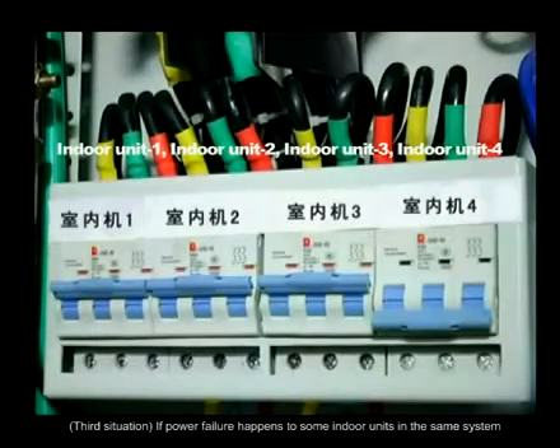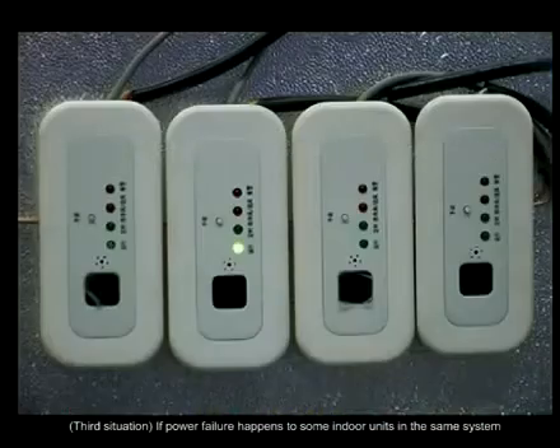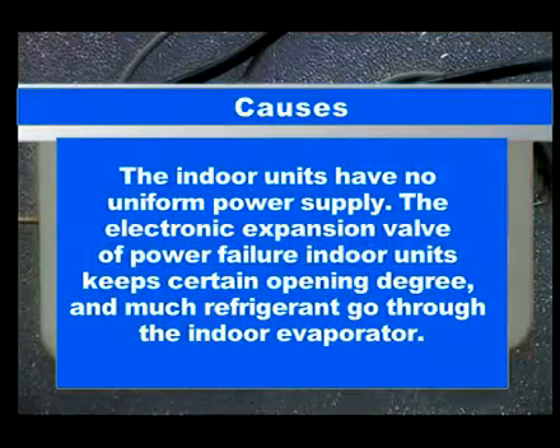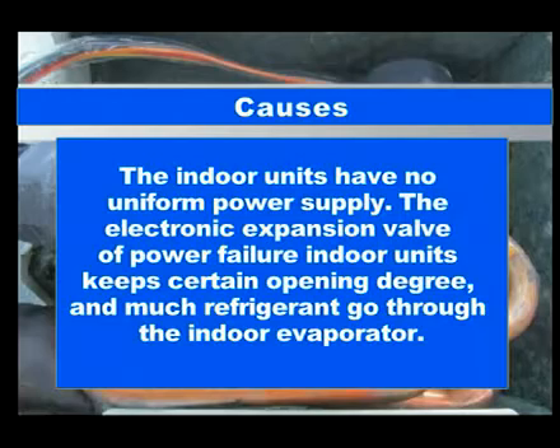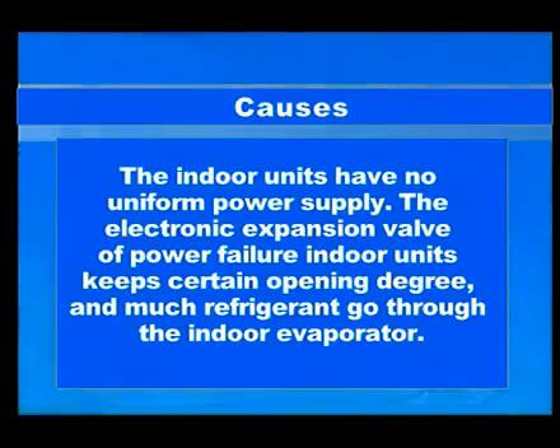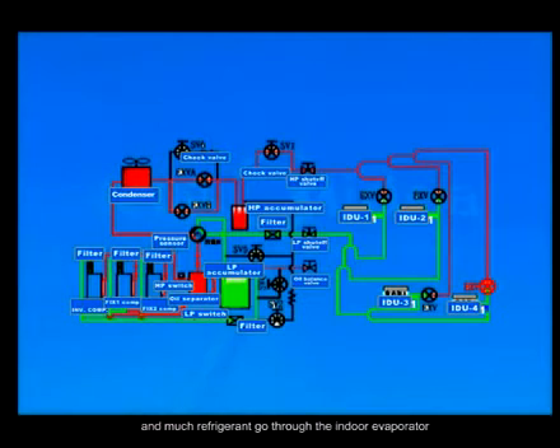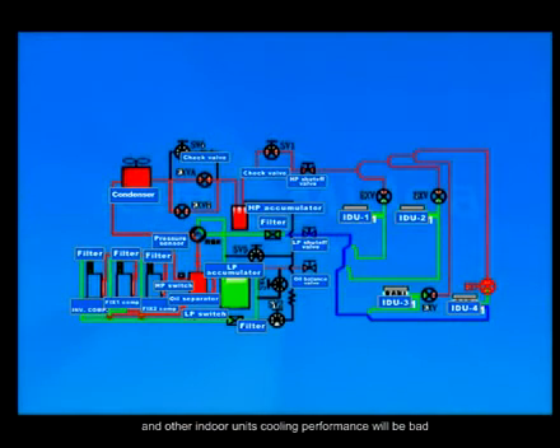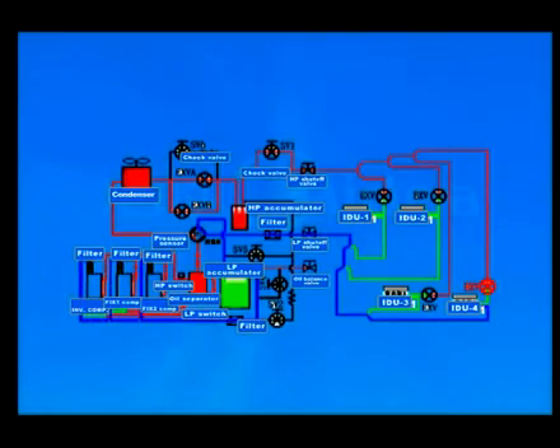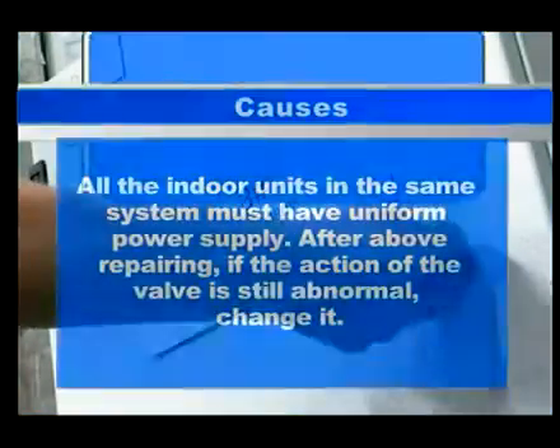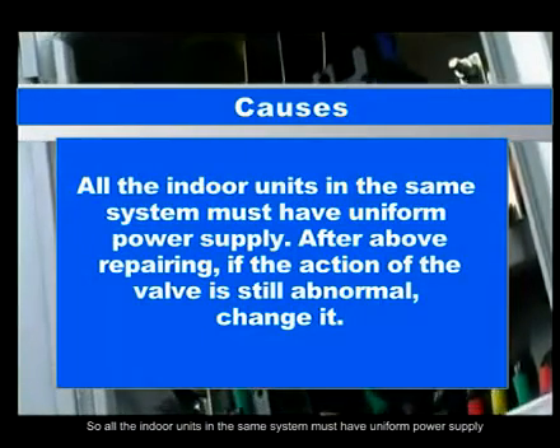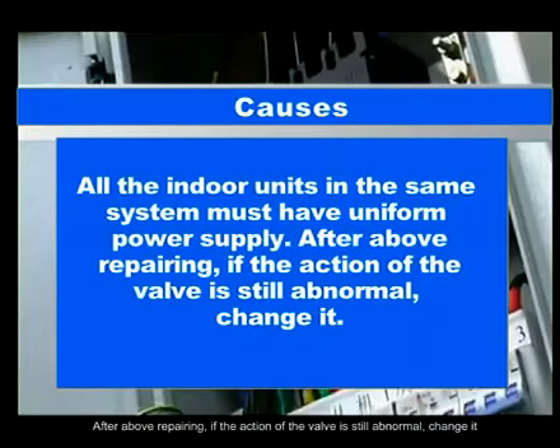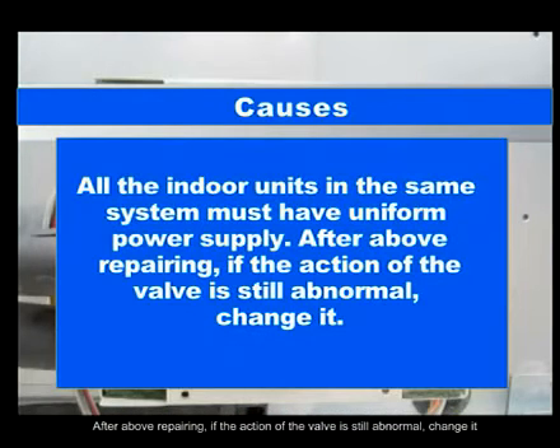Third situation. Power failure happens to some indoor units in the same system. Malfunction analysis. The indoor units have no uniform power supply. The electronic expansion valve of the power-failed indoor units keeps a certain opening degree, and much refrigerant goes through the indoor evaporator. Condensing water will appear in the indoor units, and other indoor units' cooling performance will be bad. It is also possible that much liquid goes back to the system and seriously affects the reliability of the compressor. So all the indoor units in the same system must have uniform power supply. After the above repairing, if the action of the valve is still abnormal, change it.